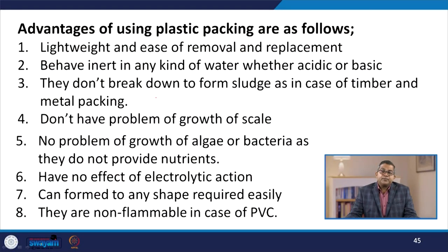Now, there are various advantages associated with the use of plastic packing. One is that they are lightweight, and removal and replacement is quite easy. They behave inert in any kind of water, whether acidic or basic. They do not break down to form sludge as in the case of timber and metal packing. They do not have a problem of growth of any kind of scales. There is no problem of growth of algae or any kind of microbial activity because they do not provide any kind of nutrients.